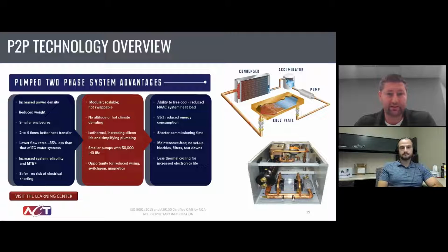Some other benefits: it's hot swappable, so the usage of quick disconnects and being able to insert and remove different componentry while the system's fully charged is a big benefit. And you'll also see some of the things we mentioned earlier. It allows for a compact system because you're running at a fraction of the horsepower of the pump compared to a single phase system. So a lot of benefits you have here. There are also thermal performance benefits, higher heat flux and isothermality. What we do at ACT is take the system design parameters and come up with a solution that'll create an economical design for whatever situation you need. In certain cases, we have to design to the extremes of isothermality and safety and performance.